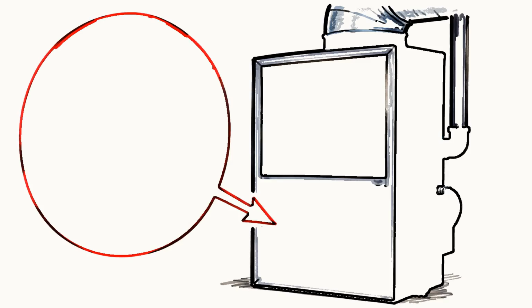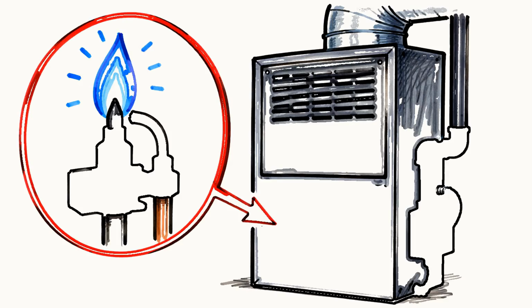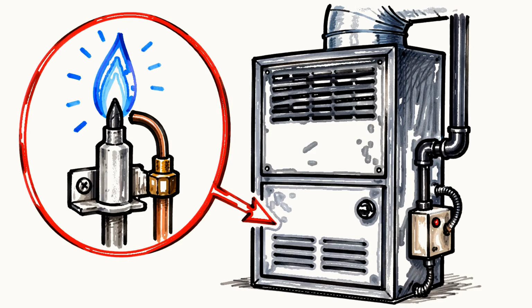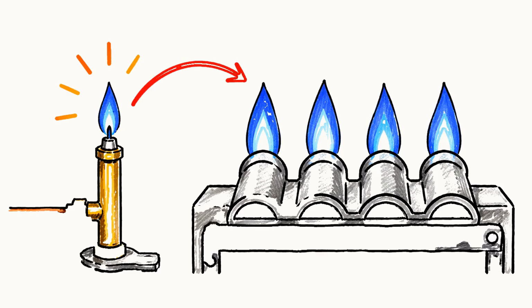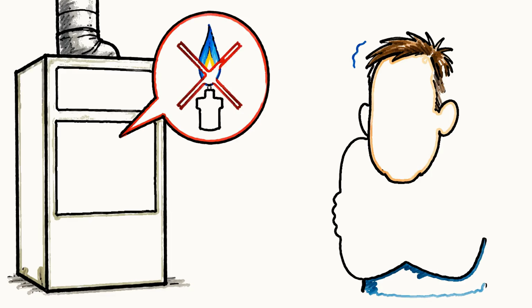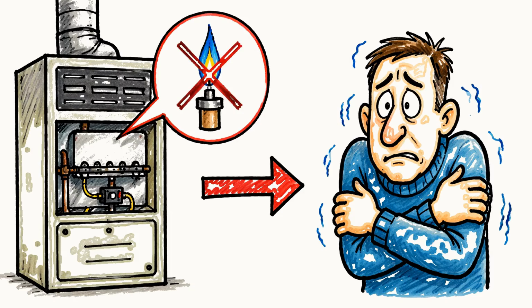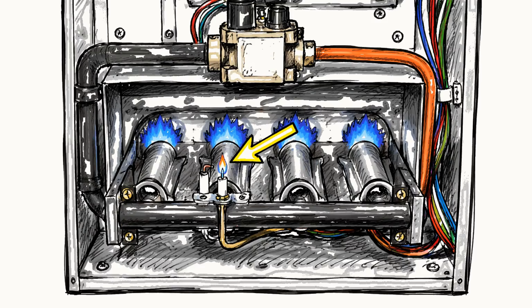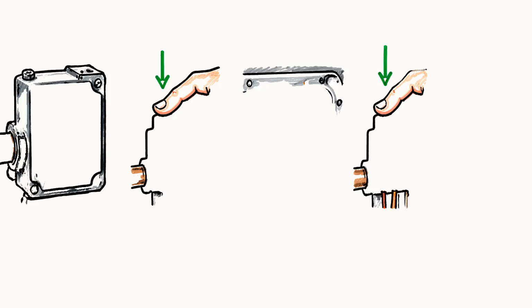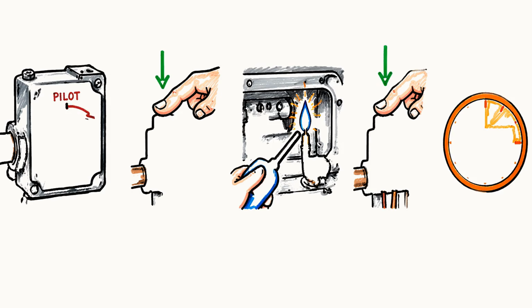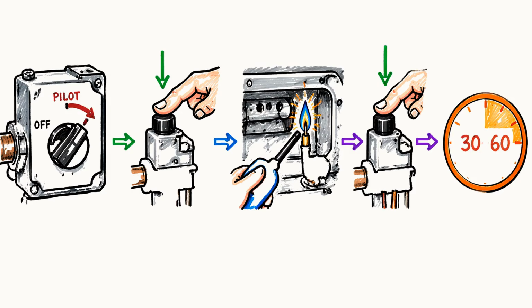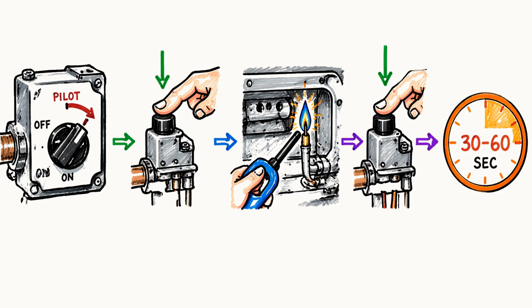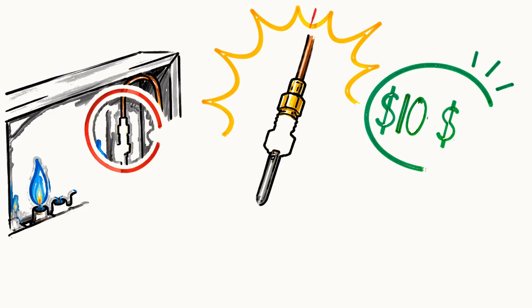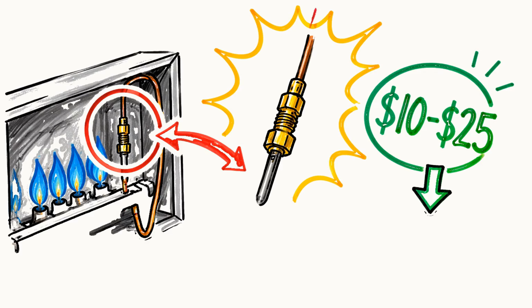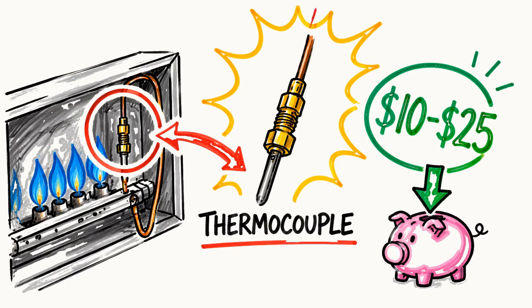If you have an older furnace, and by older I mean built before roughly 2010, you might have a standing pilot light. That is the little flame that stays lit and lights the burners when heat is called for. If that pilot blows out, you get no heat at all. Look for the small flame near the burners. If it is out, there are relighting instructions printed right on the furnace, and it is usually a matter of turning the gas knob to pilot, holding the button down, lighting it, and keeping that button held for 30 to 60 seconds. If you relight it and it will not stay lit, the part called the thermocouple is failing, and that is a cheap fix, usually $10 to $25 for the part.